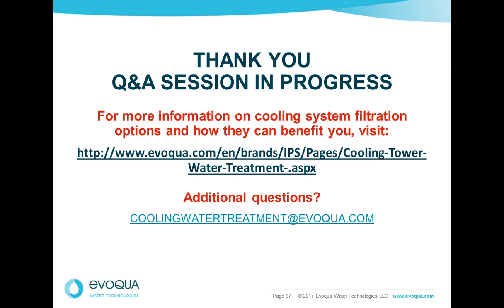All right. Next up, are there any sidestream filters that can remove small amounts of oil and grease, say 10 parts per million, or is 10 parts per million not really a problem for cooling towers? So 10 parts is not an enormous amount. With a media filter, like a high efficiency sand or other media filters, a small amount of oil is generally not a problem, but 10 parts is probably starting to push it. You'll end up coating the media and it becomes difficult to clean. In those cases, you could use a self-cleaning screen filter. They'll handle maybe 20, 25 parts of oil without starting to plug themselves up.